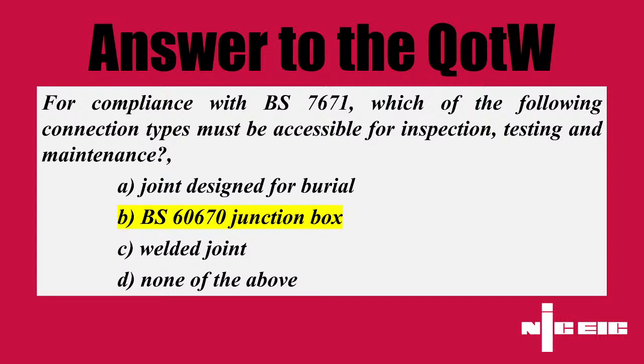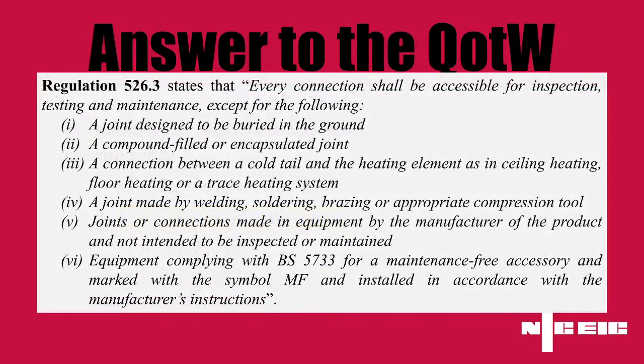The type of connection which must be accessible for inspection, testing and maintenance out of that list was a BS 60670 junction box, an old style junction box. Where are we deciding that answer from? Let's take a look - this is really driven by regulation 526.3. So George, what kind of things does regulation 526 tell us that we can make sure doesn't have to be accessible?